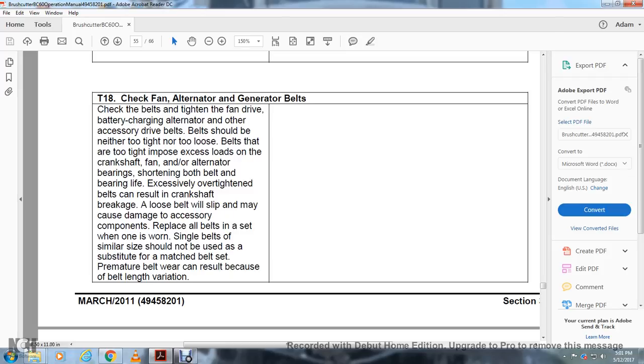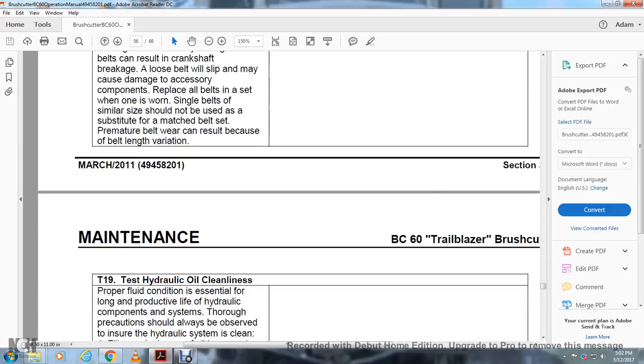Replace all the belts in a set when one is worn. Single belts of similar size should not be used as a substitute for a matched belt set. Premature belt wear can result because of belt length variation.